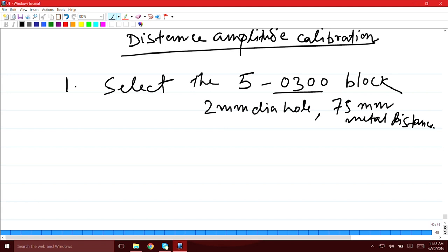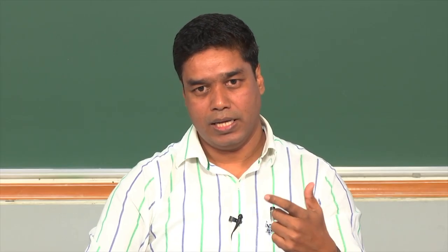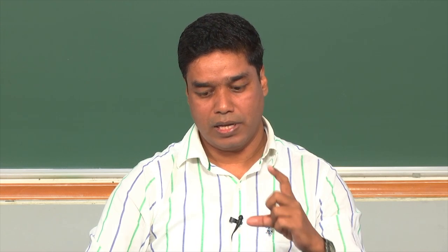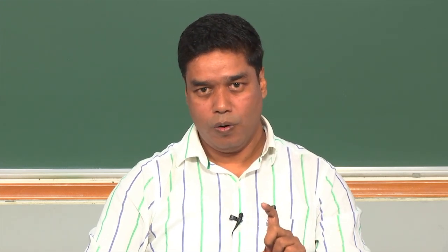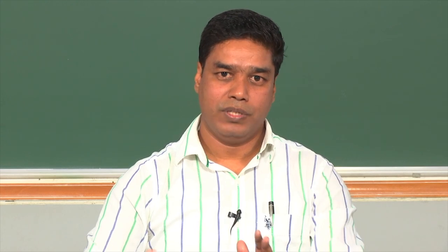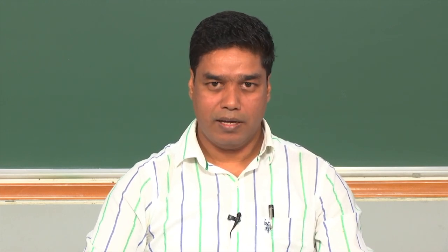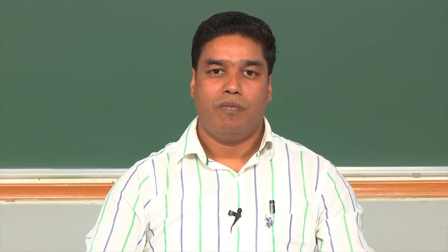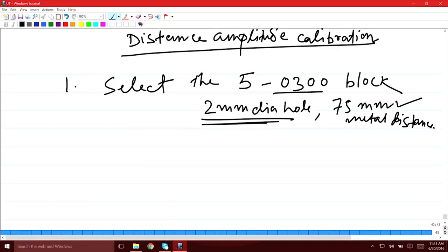We are going to keep this hole size constant and then vary the metal distance by selecting other blocks, collecting a number of data points in terms of distance. We collect the intensity of the echoes coming from these flat bottom holes as a function of metal distance, and with that data we can plot a curve used for calibrating the distance.